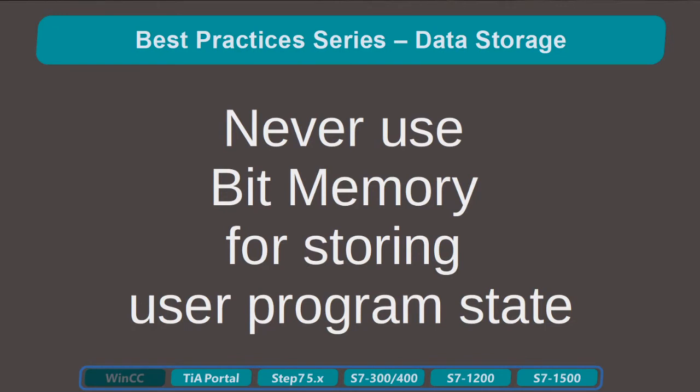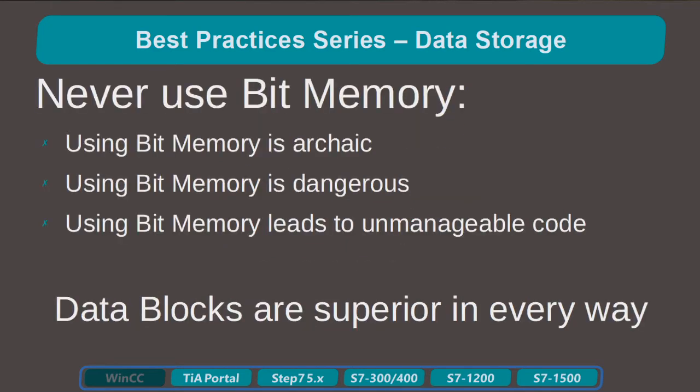In this video we'll discuss the use of bit memory and why its use in modern programs is a bad idea. You should never use bit memory because it is archaic. It's part of the old hardware of the old PLCs and it's only in the new ones for backward compatibility. Using bit memory is dangerous, it has global scope and it's difficult to move things around.